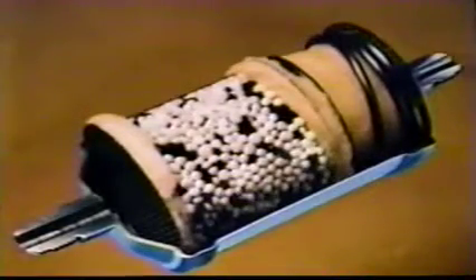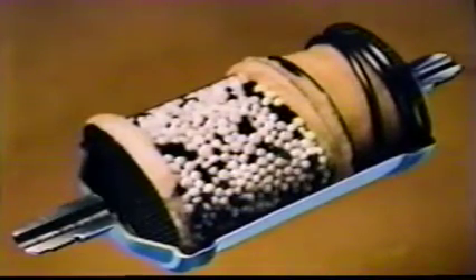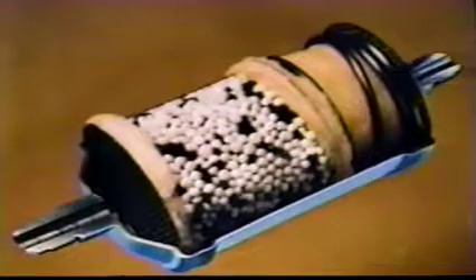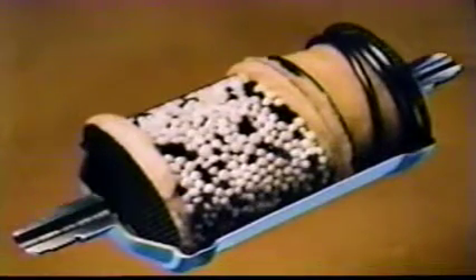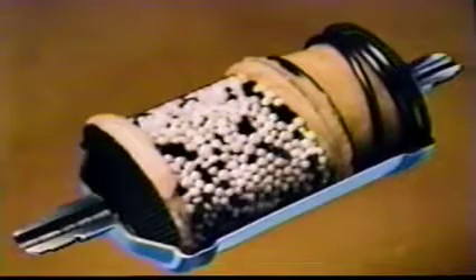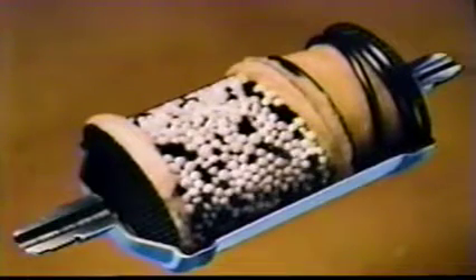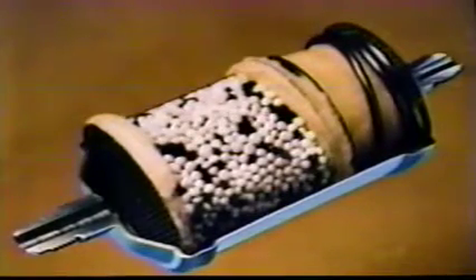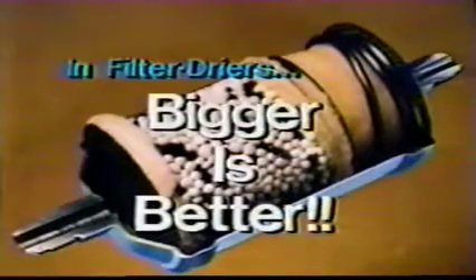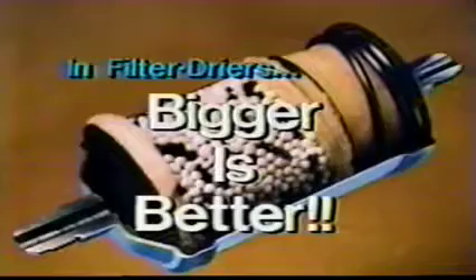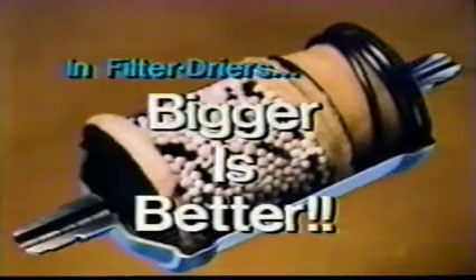All filter dryers will follow the rule that the larger they are, the more contamination they will remove. We also know that as a filter dryer goes up in size, its internal pressure drop is lower. Since keeping pressure drop low is a must for all filter dryers, it makes sense to use as large a filter dryer as space will permit. This is particularly true for the installation of a filter dryer after a burnout.